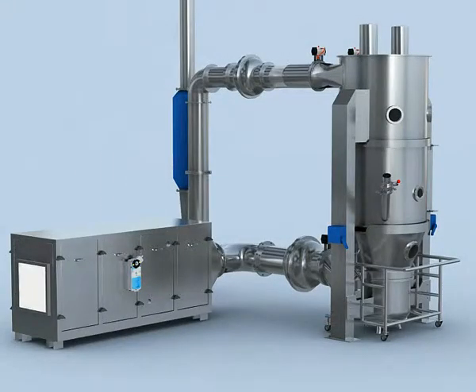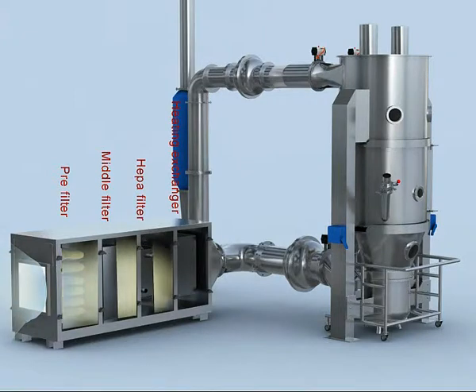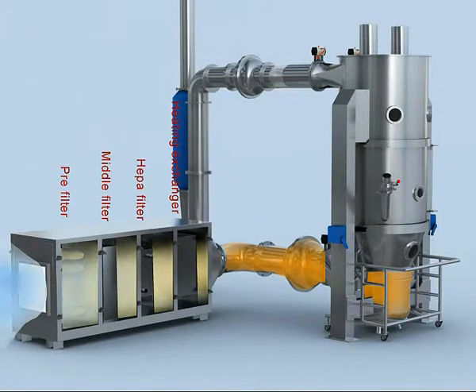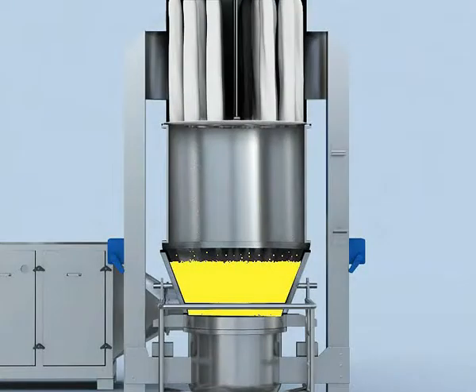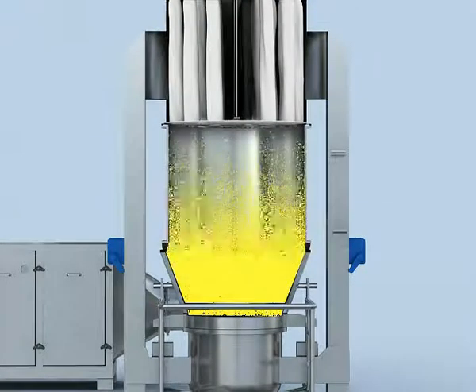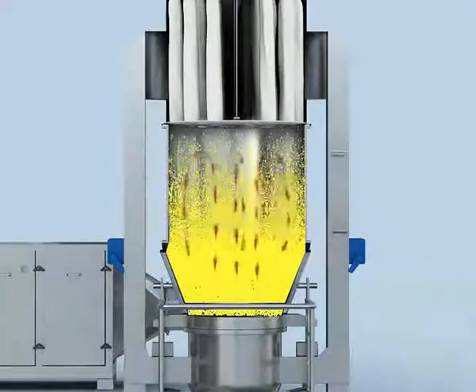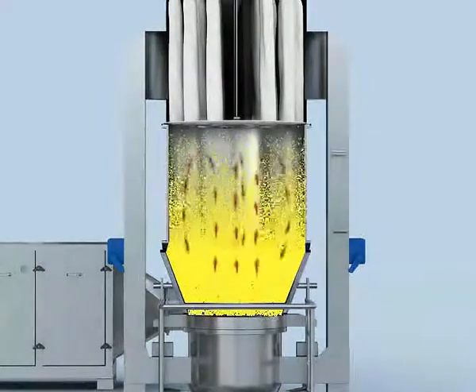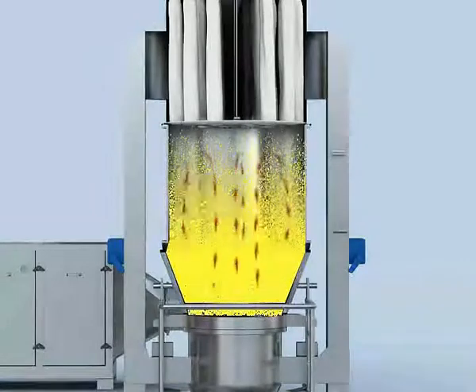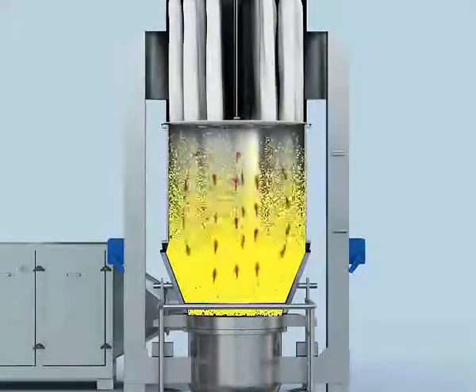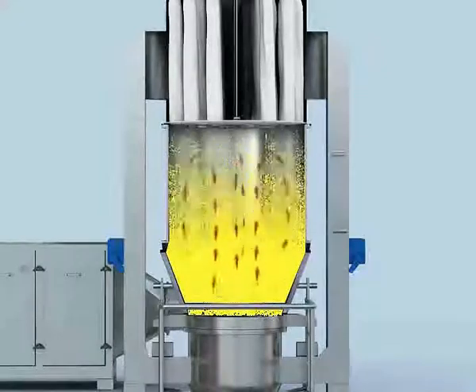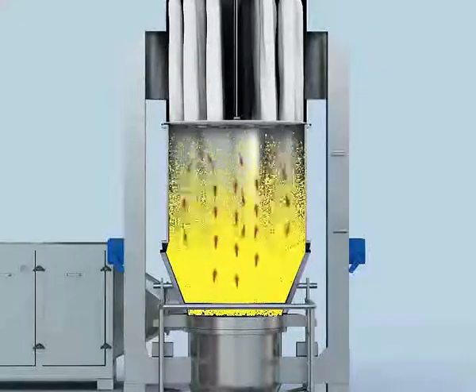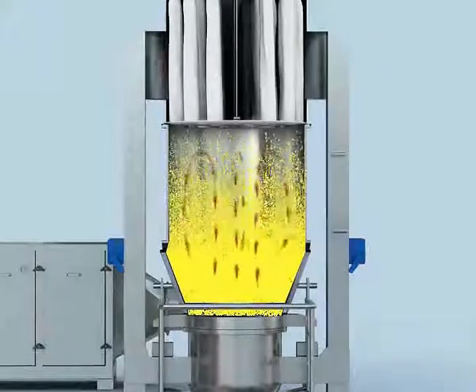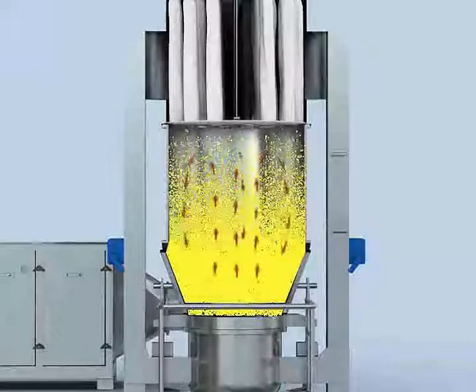chamber. Upon finishing material transfer, the charging valve closes and the drying process starts. Intake air is guided into the fluid bed lower chamber through the primary filter, medium filter, heat exchanger, and HEPA filter. The material is then blown up and realizes fluidization. Inlet air temperature is adjusted by a PID regulating valve by controlling the hot and cold air proportion. Moisture is evaporated and evacuated under the continuous heat exchanging inside of the chamber, and drying is then achieved.